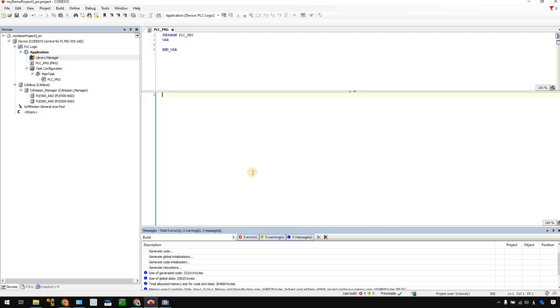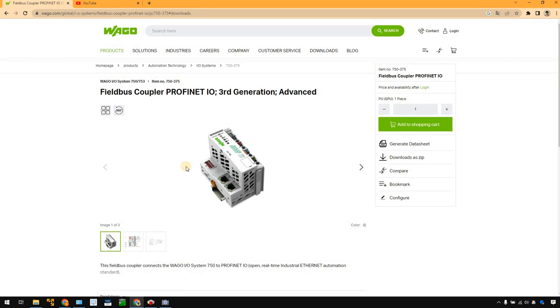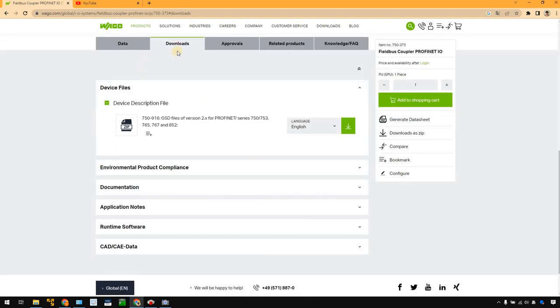Before you configure the Profinet network — as I showed you in many Profinet tutorials before — you need to download the GSDML file from the manufacturer's website. Go to Google and search 750-375 to find the WAGO fieldbus coupler, Profinet IO, 3rd Generation, Advanced, and go to Downloads and download the device description file. You need this file to import inside your CODESYS IDE.